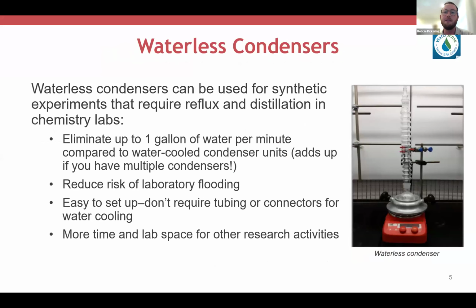A common use of single pass cooling within labs is for condensers that are typically used in chemistry labs. Condensers are used for synthetic experiments that require reflux and distillation. There are now a few different models of waterless or air-cooled condensers on the market. Most water-cooled condensers can easily be swapped out with waterless models, which also provide a multitude of benefits. Primarily from the water side, you're eliminating that constant stream of water of up to 1 gallon per minute. And as we just discussed, that results in a significant amount of cost savings.